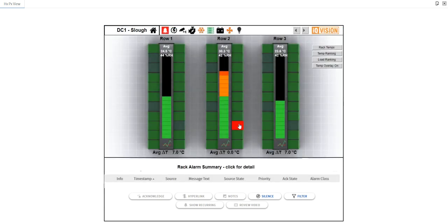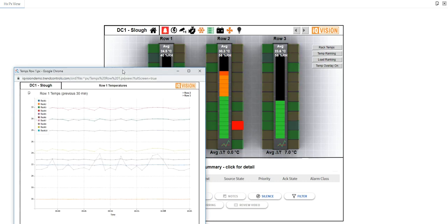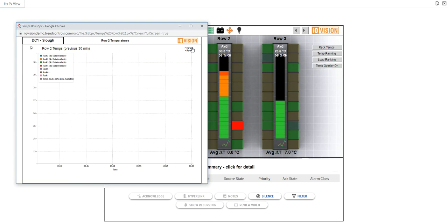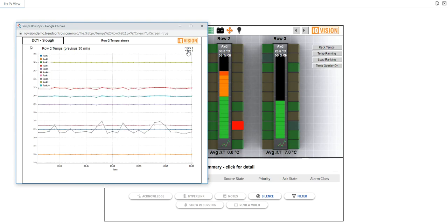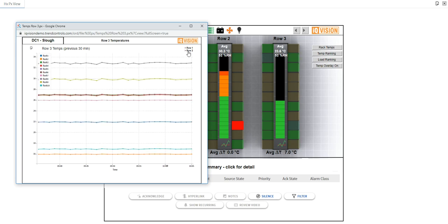This will pick out where there are big changes in temperature. You can see in the last hour, as I'm speaking, we've had quite a compared to the other range here, we've had quite a change. So we can do an awful lot in this graph view. That is something the operator needs to go and look at. I've put a few more graphs in here. We have rack temperatures just so we can go and see. So that's row one, row two. And no surprise that one of them is much higher than the others. And row three. These are all averaged over the previous 30 minutes. So it's a rolling 30 minute window.